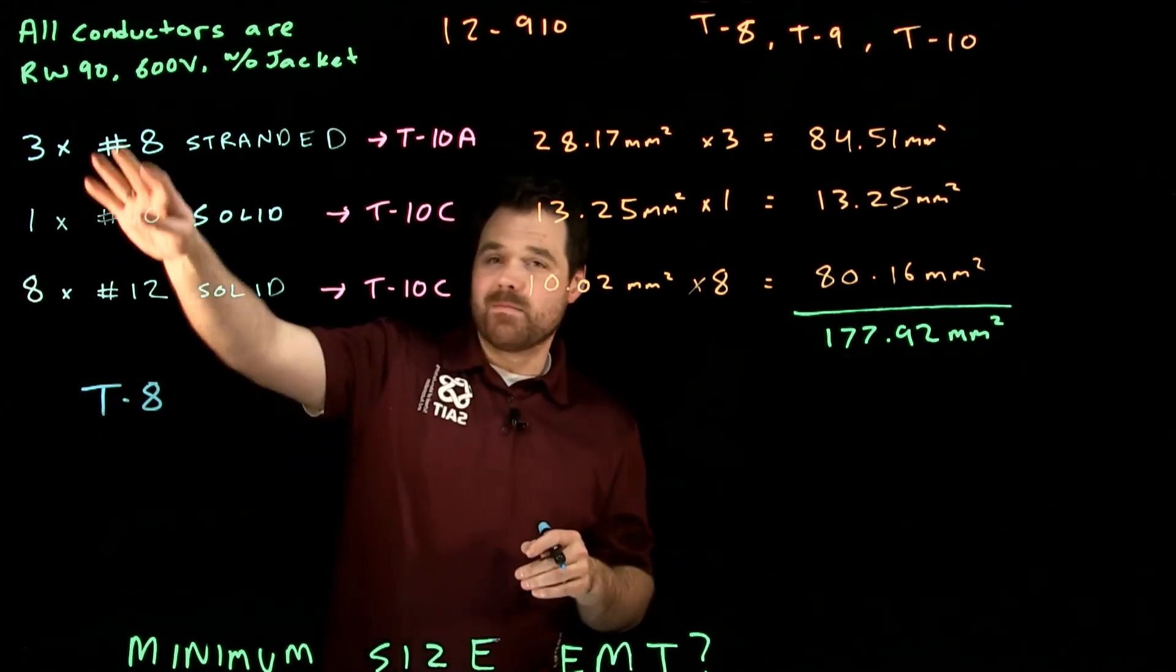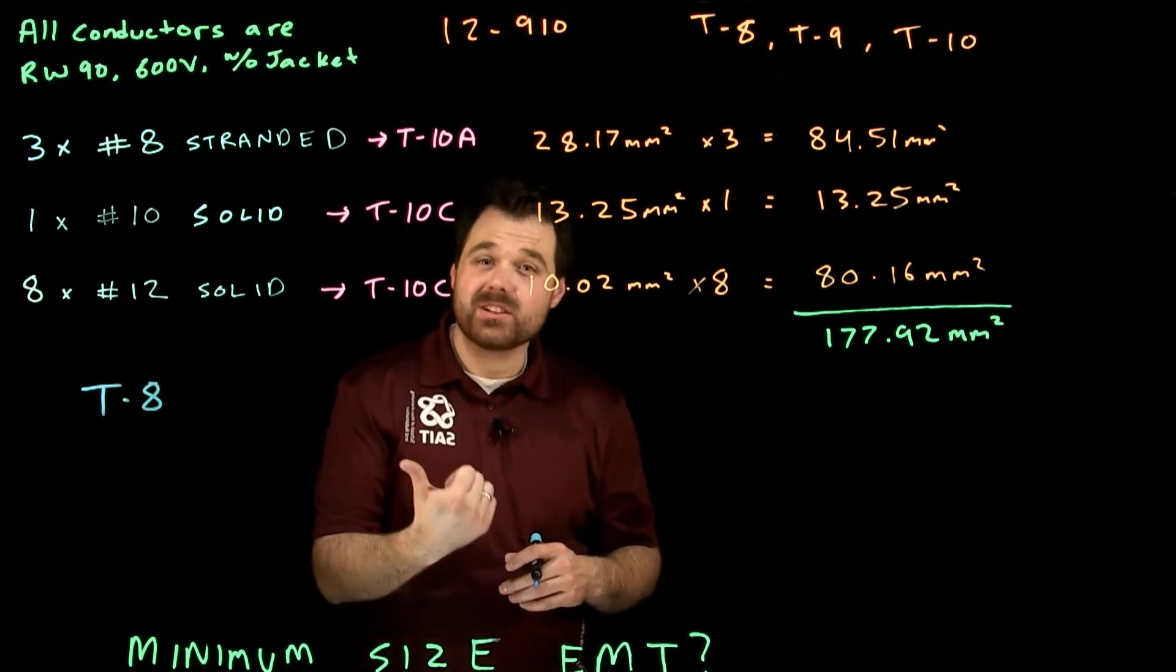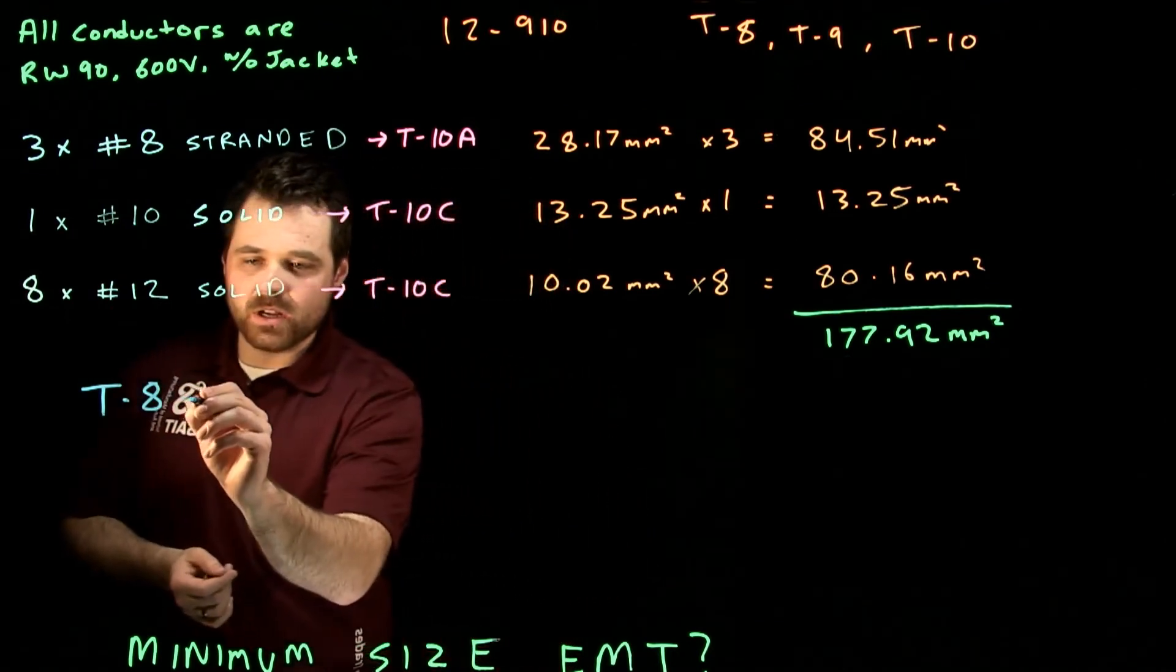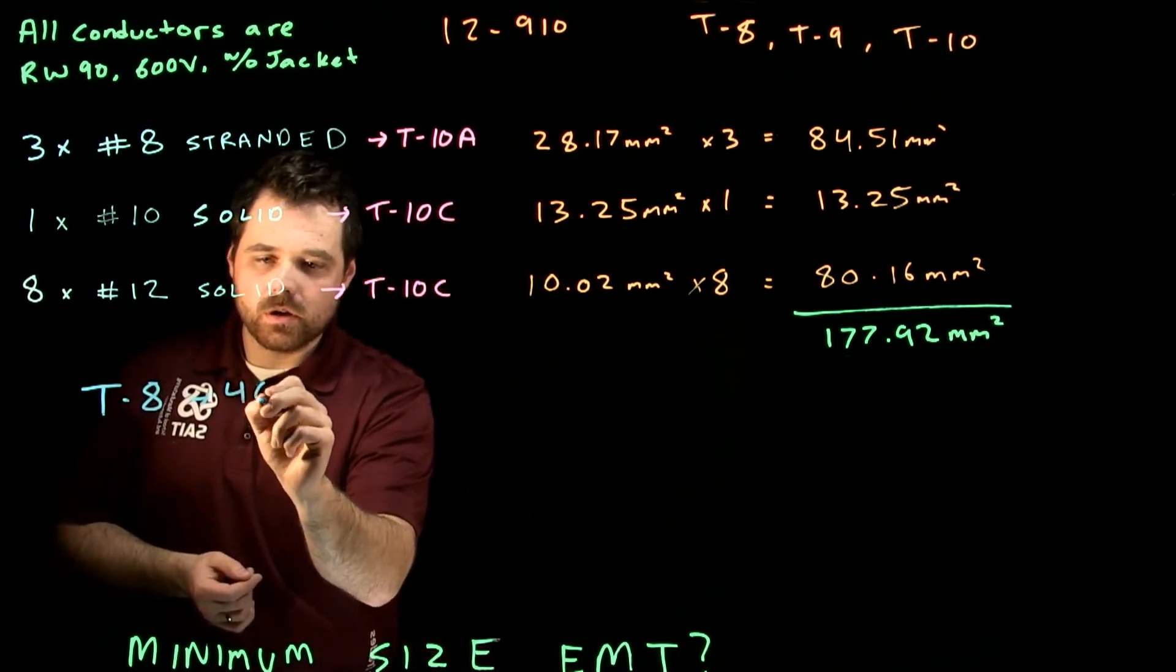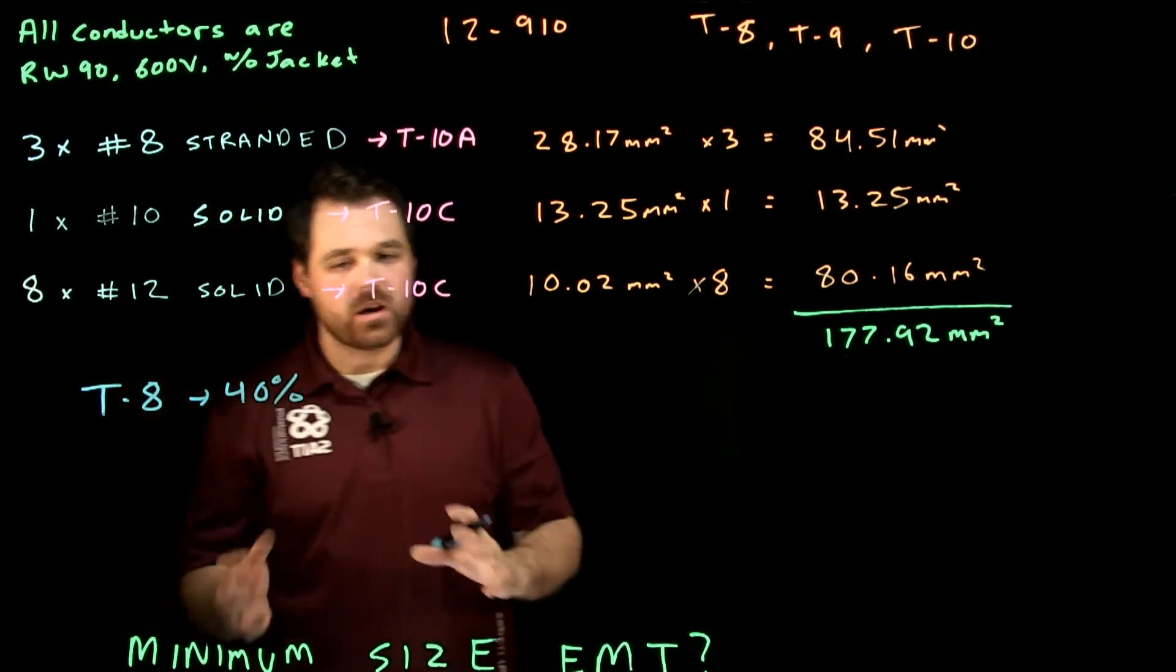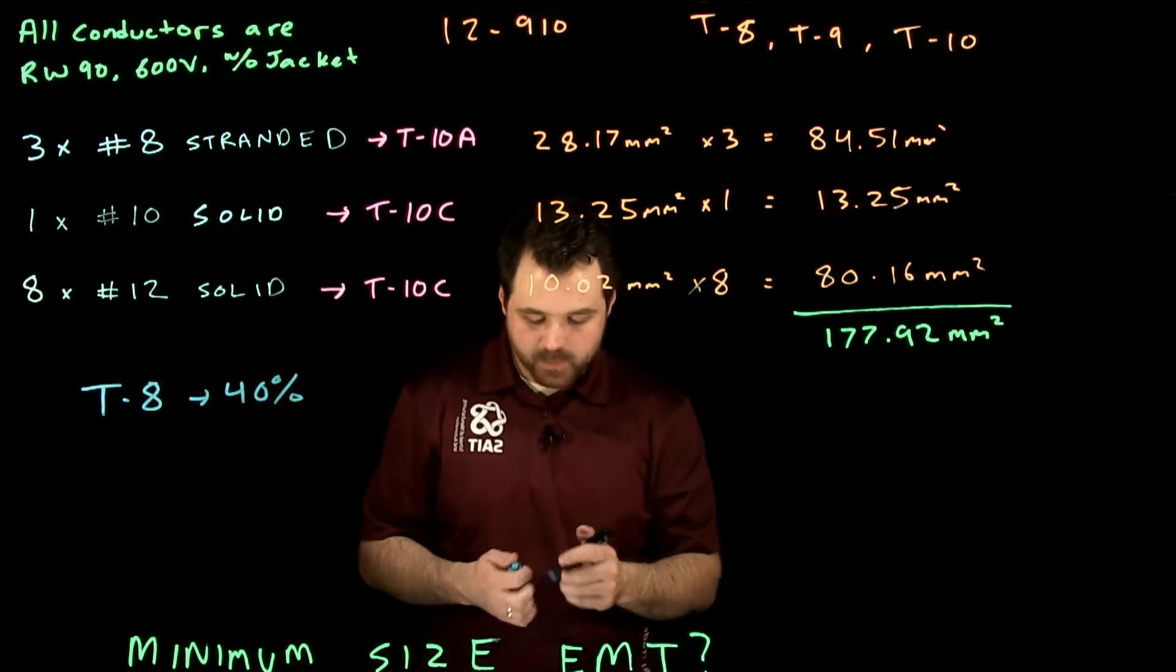So because we have more than four conductors, we're using a non-lead sheathed conductor. Table 8 tells us we can go 40% full. So my conduit can be up to 40% full. Perfect.